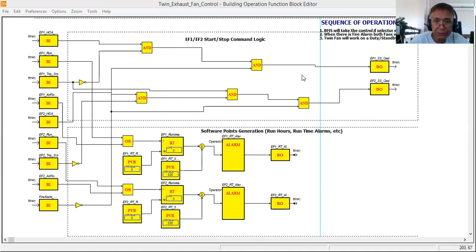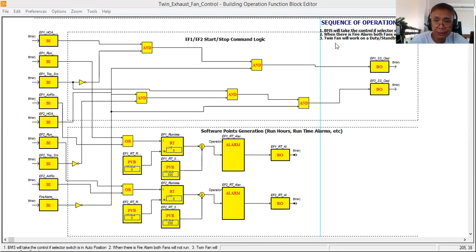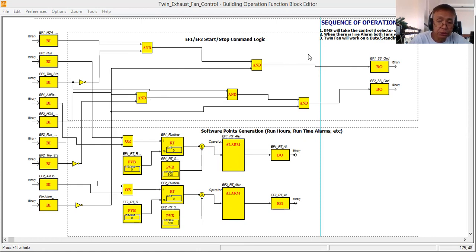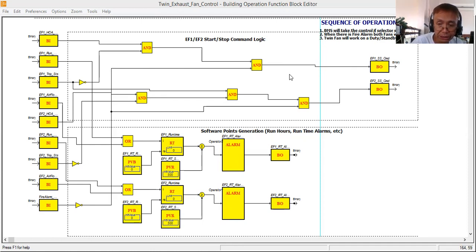This first triangle is the EF1 start/stop command logic — it will start and stop the fan as per the sequence of operation stated in the program. Currently I have a very simple sequence of operation. It will become more complicated if I inject more conditions or add sequencing, so I want to keep it simple especially for beginners.